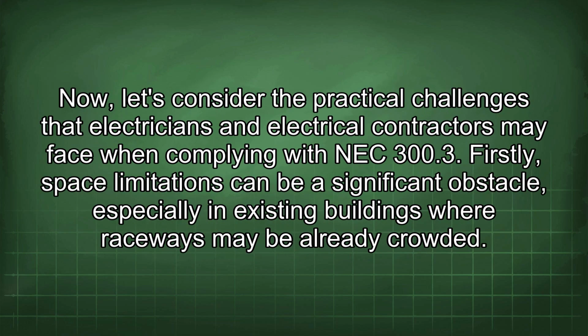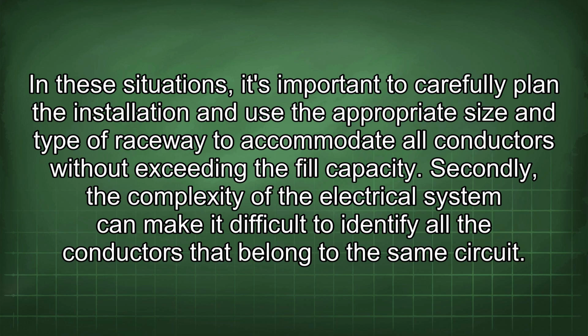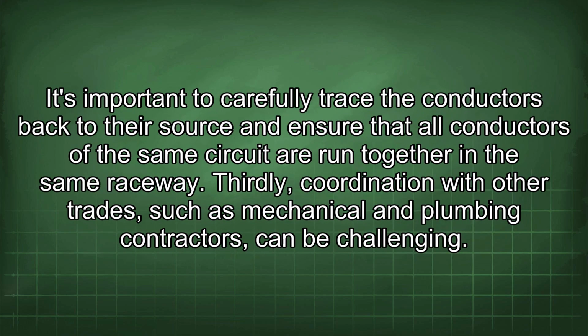Now, let's consider the practical challenges that electricians and electrical contractors may face when complying with NEC 300.3. Firstly, space limitations can be a significant obstacle, especially in existing buildings where raceways may be already crowded. In these situations, it's important to carefully plan the installation and use the appropriate size and type of raceway to accommodate all conductors without exceeding the fill capacity. Secondly, the complexity of the electrical system can make it difficult to identify all the conductors that belong to the same circuit. It's important to carefully trace the conductors back to their source and ensure that all conductors of the same circuit are run together in the same raceway.